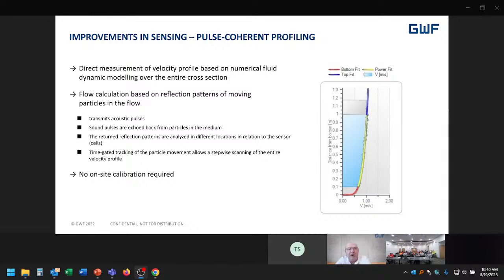Well, if we're listening at different times for that echo, you can actually start to find out what's going on at different points within the channel. So suddenly we're able to say, okay, we can break the channel into multiple areas and calculate or measure the velocity of the flow at different points within the channel. That's important. So I mentioned with the radar that you're doing a spot measurement. You're only measuring the velocity at that point, and we have to correct for how the flow will be going through the rest of the cross-section of the channel. But by measuring different points within the channel, we're able to actually see a flow velocity profile for the channel.